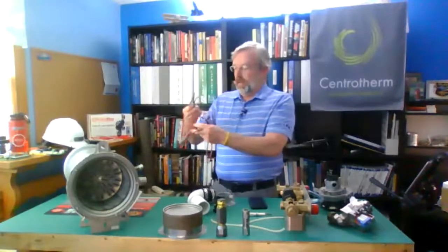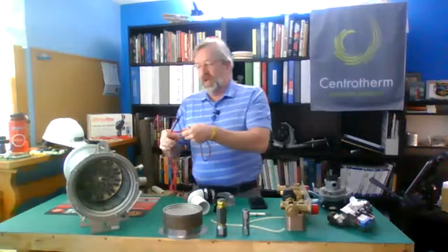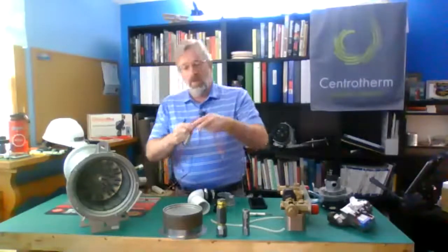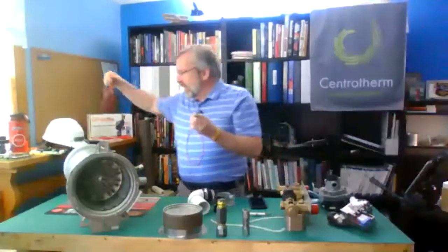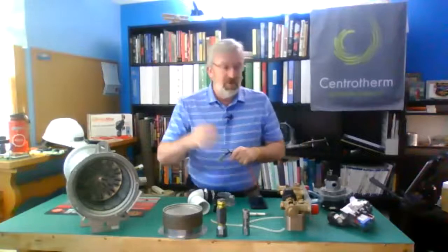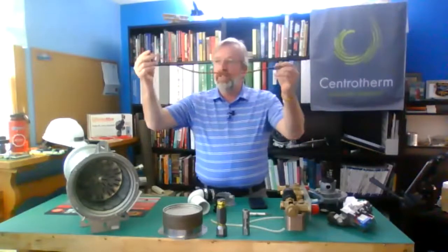again with our meter. And what you're going to do is take your meter at this point in time. I'm going to go to ohms, the resistance. That's that funny looking horseshoe thing. I'm going to get in each end of my ignition cable. Now we have a resistor in here. The purpose of that resistor is really kind of tamping down some electromagnetic interference that we can create inside the boiler, or I should say inside the cabinet, between the board and the fan. So we reduce that with this. There's a potential you could have a bad cable. This should be 1,000 ohms. If it's 700, stop, replace this, go to the next thing. If it's 1,000 though, this is okay.